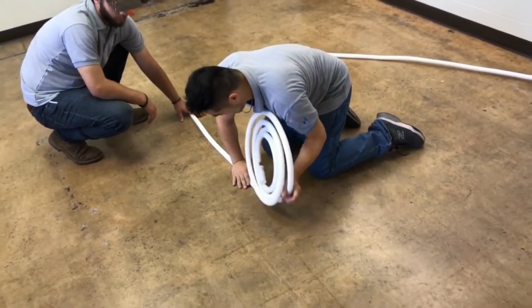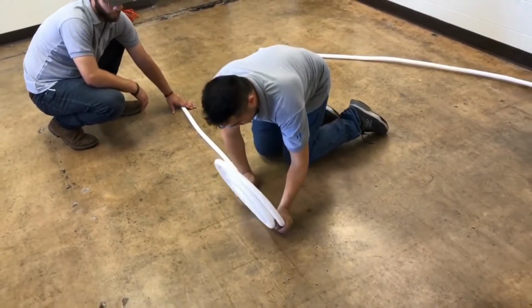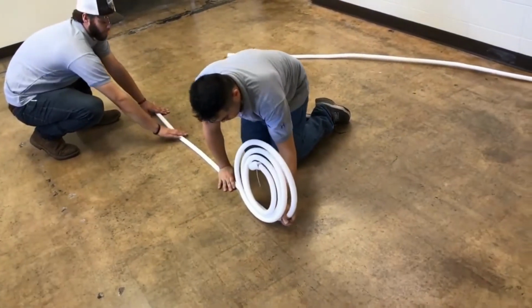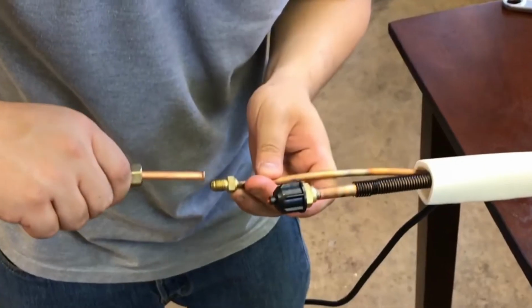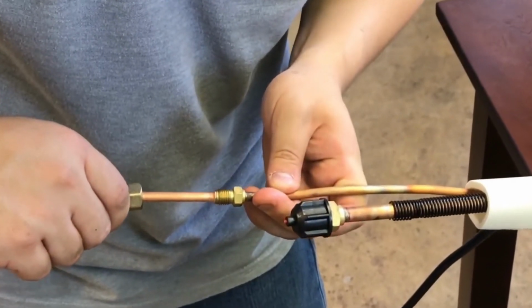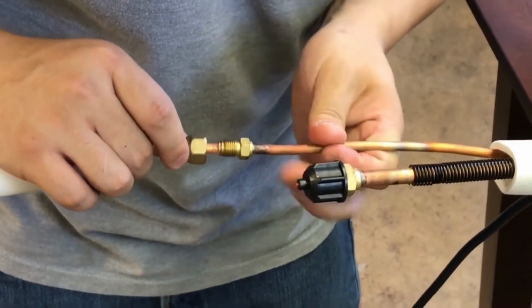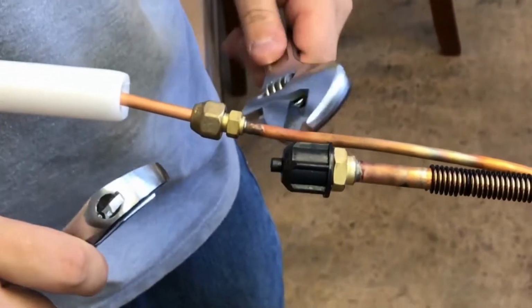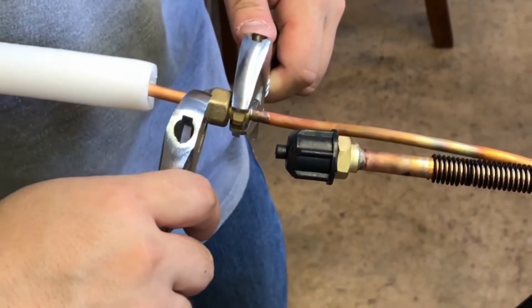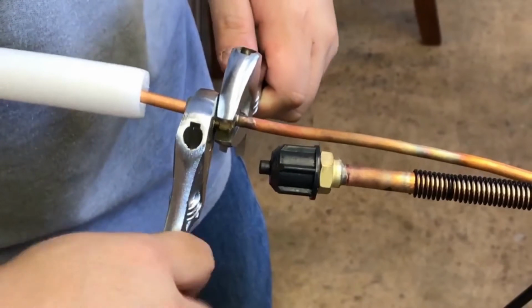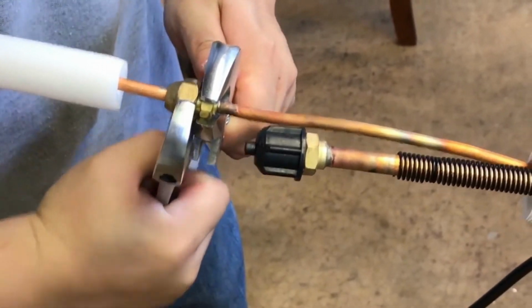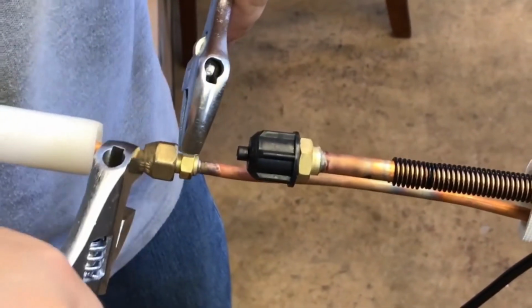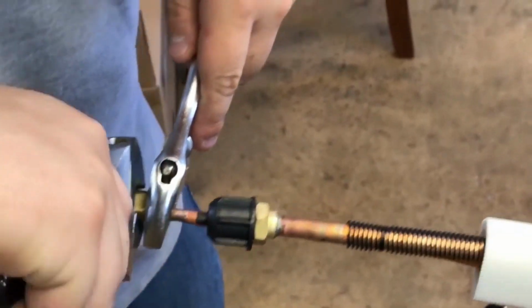Now carefully unfold the refrigerant pipe, making sure not to crimp the copper tube in the process. Connect the flared copper ends of the line set to the pipe joint connected to the air handler, using the adjustable wrench to hold the piping joint and prevent twisting. Place the torque wrench on the union nut and tighten to the setting specified in the owner manual.